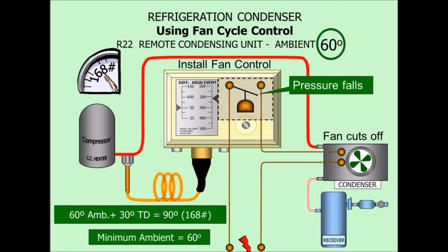If you set it below 30, what's going to end up happening is the fan is going to cycle on and off quite rapidly, and you're going to burn out your condenser fan. If you set it for above 50, it's too long of a period for the fan to be off, and that causes wide swings in the head pressure, and those wider swings in the head pressure can also cause metering problems. So you want to keep that differential pressure between 30 and 50. The initial setting before you dial it in, you should put it at 40, and that's a good place to start. Let's take a look at the settings that we have right here.